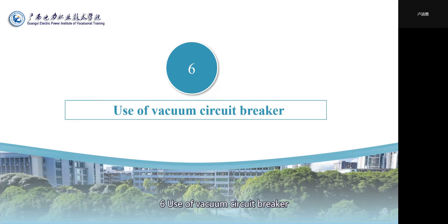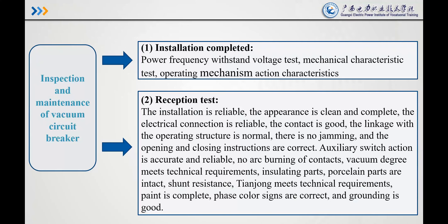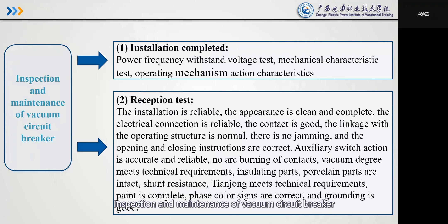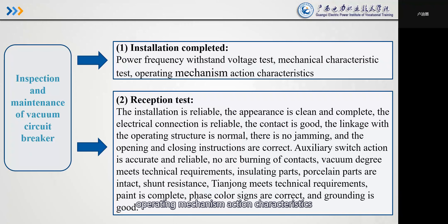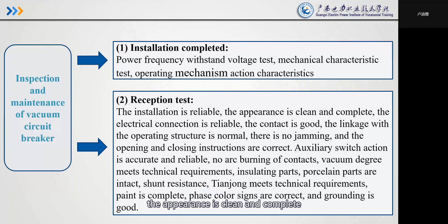Section 6: Use of vacuum circuit breakers. After installation is completed: (1) Power frequency withstand voltage test; (2) Mechanical characteristic test — operating mechanism action characteristics; (2) Reception test; (3) The appearance is clean and complete; (4) The electrical connection is reliable; (5) The contact is good; (6) The linkage with the operating structure is normal.